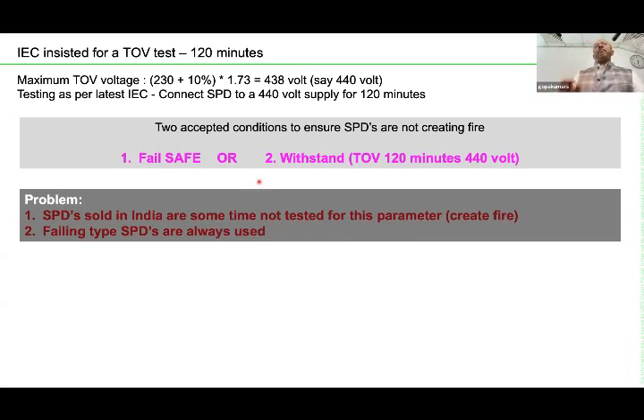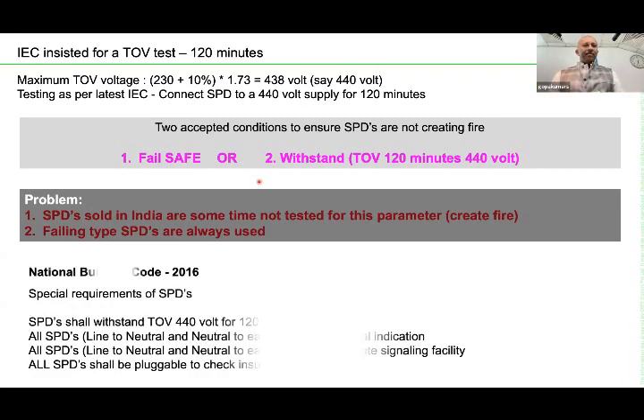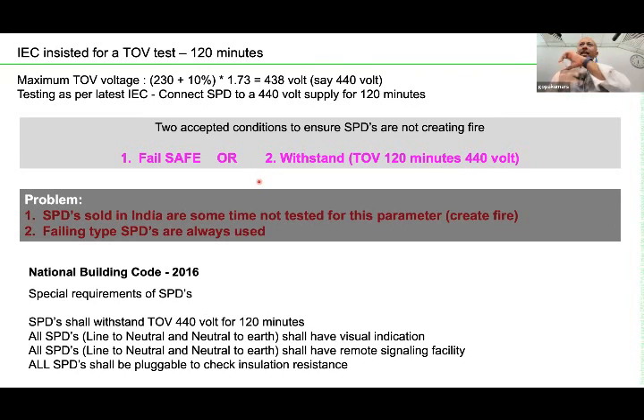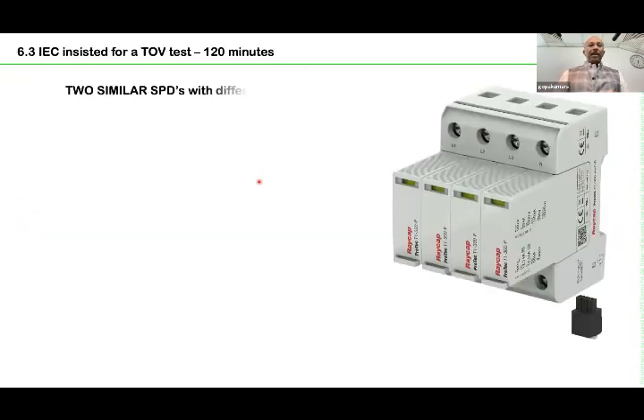When you buy an SPD, you can also look at this particular parameter and check whether the SPD is able to withstand this voltage or not. Otherwise, not because of a transient condition, but because of neutral isolation, your SPD will blow. And then you have to replace it. Whereas if you go for an SPD with this TOV withstand, then you will get a much better life. So only these SPDs are permitted. For example, in India, we included this in the National Building Code. All SPDs should be able to withstand this particular parameter.